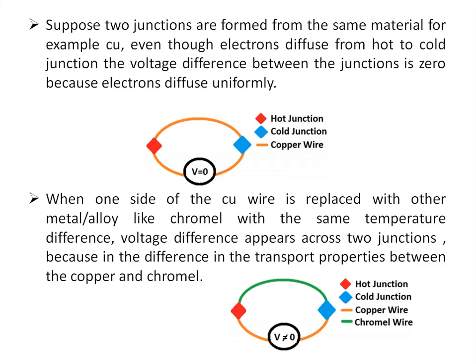If the two materials forming the two junctions are the same, no EMF will be produced because the Seebeck coefficient for both materials is equal and the net EMF difference is zero. When one copper wire is replaced with a metal alloy like chromel, which has a different Seebeck coefficient, the two junctions will have different EMFs. This creates a net EMF that is proportional to the temperature difference between the two junctions, and the voltage across each metal element depends upon its Seebeck coefficient.